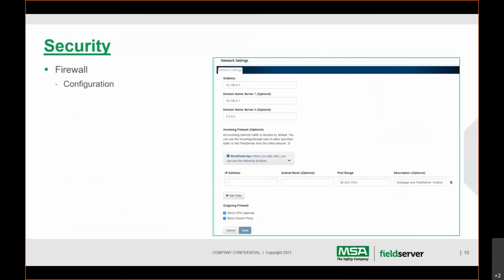Okay, now we're getting into the configuration of Ethernet 2, specifically for incoming connections. So on the right, you're looking at the configuration page, which is the web page built into the field server product. So you go in, you can set up the IP address, you set up the DHCP, you set up subnets, DNS servers, and then you have the ability to set in routing tables. So in this example here, in the IP address, we've got a star. Star basically meaning all IP addresses with ports 80 and 443 is web browsers. So it'll allow any product with a web browser to browse to it.